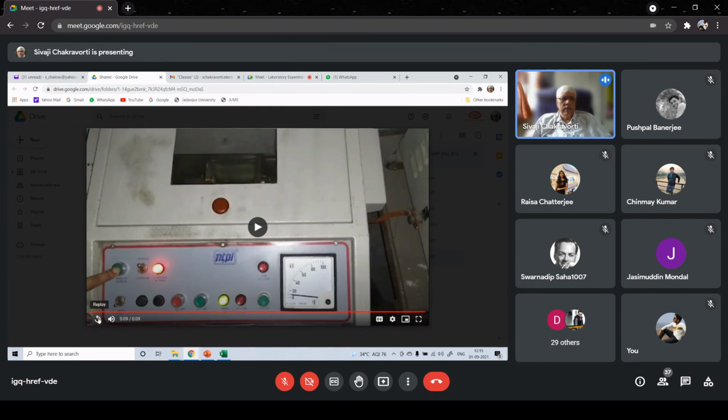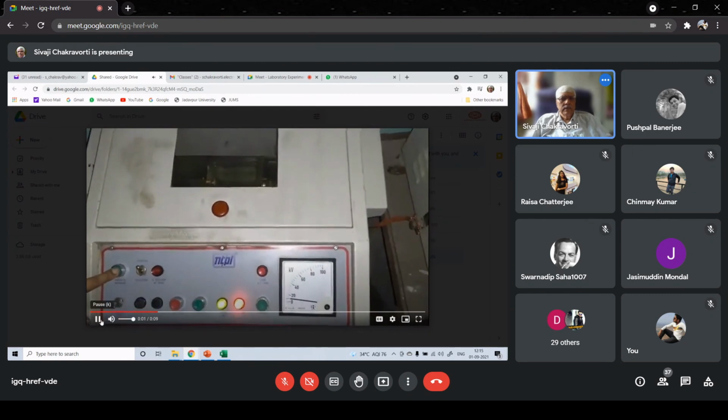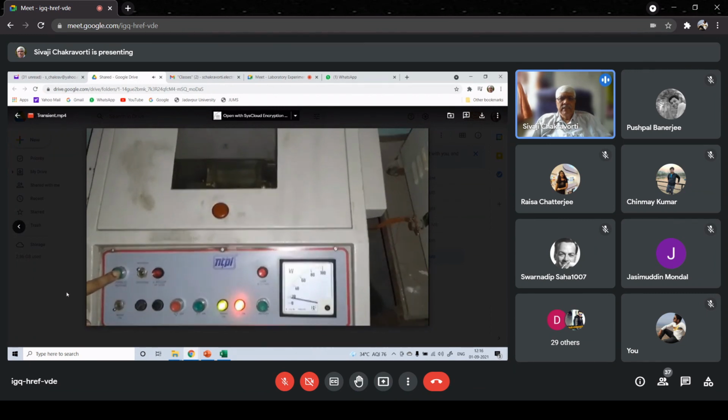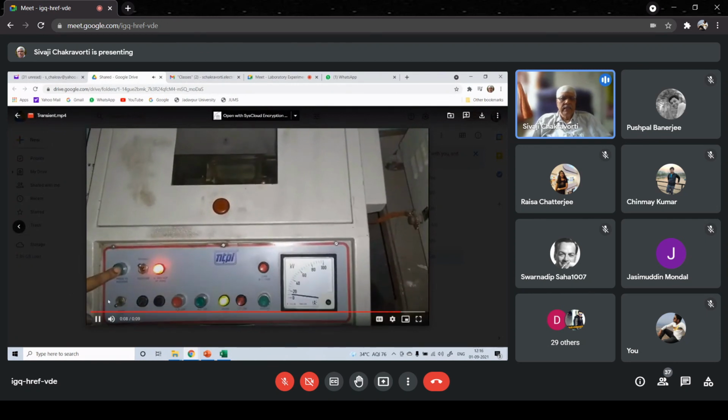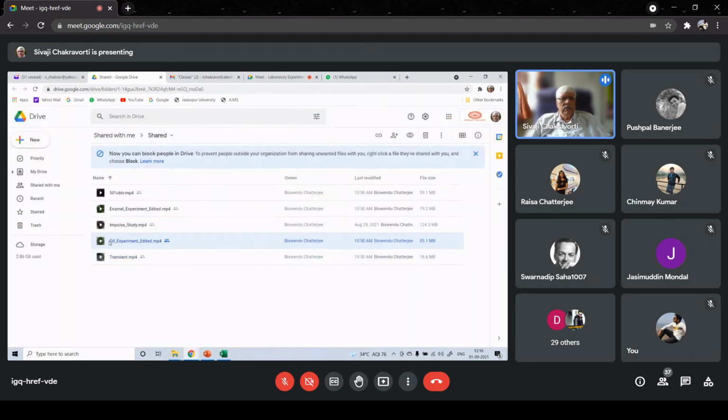So again, look at it. Yeah, I think now you can see it. Yeah, here, that's the transient breakdown. But there is no complete breakdown because the voltage is still increasing. See, voltage is still increasing. See, now the complete breakdown has taken place, and we note down this voltage, this final value. And how do we perform the test?